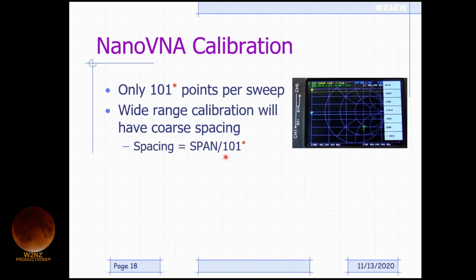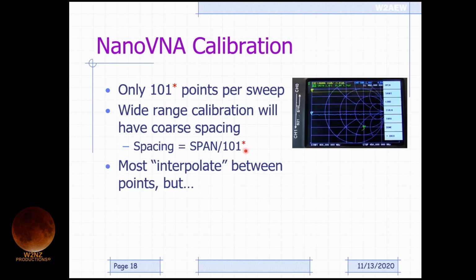If I did a calibration from 1 meg to 30 meg, so a 30 megahertz span, I'm going to divide 30 megahertz by 100, right? I'll have a 300 kilohertz spacing between my calibration points. Well, some of the HF bands aren't even 300 kilohertz wide, so you won't even have a calibration point inside a particular band of interest. But again, with some versions of firmware, you can go up as high as 401 points, or the external PC application allows you to have more points as well.